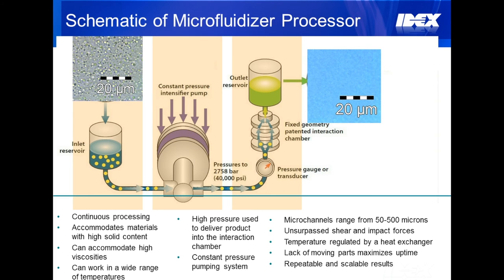One of the key characteristics of the microfluidizer processor is the constant pressure intensifier pump. This is important because it delivers all of the material at a very uniform pressure profile to the interaction chamber. The interaction chamber is the heart of our microfluidizer processor. It is a fixed geometry microchannel, which ensures that all of your material is being processed at a very consistent shear rate.